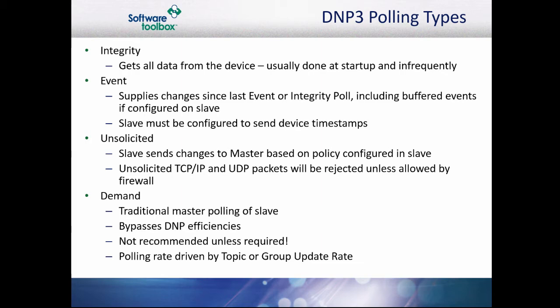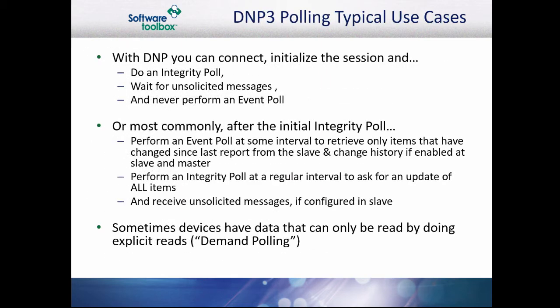There are a few standard use cases that we encounter regularly. First, you can connect your HMI/SCADA causing the DNP3 stack to initialize the session. Then, during initialization, an integrity poll is performed. After the integrity poll, we only listen for unsolicited messages, never performing an event poll.